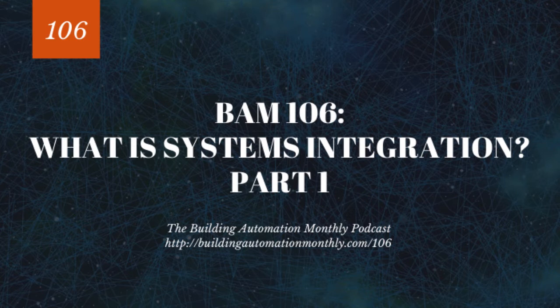So it goes device, objects, properties, right? That's how a BACnet thing works. If you think about it, a car has a bunch of doors, and the property may be number of doors. So the device may be car, the object may be door, it may be tires, it may be engine, and then the properties are the details of those objects.